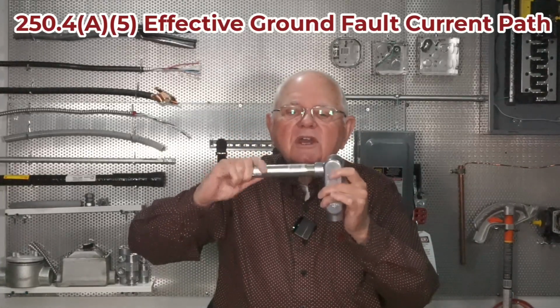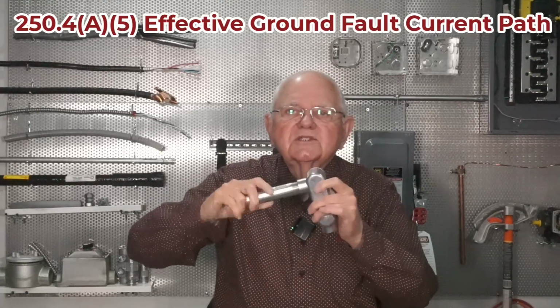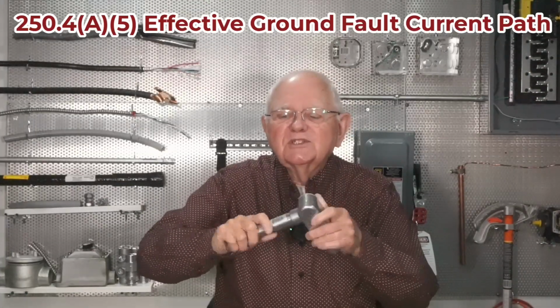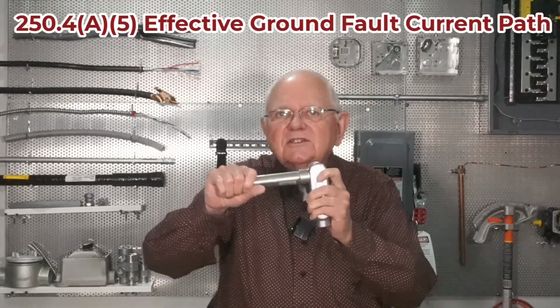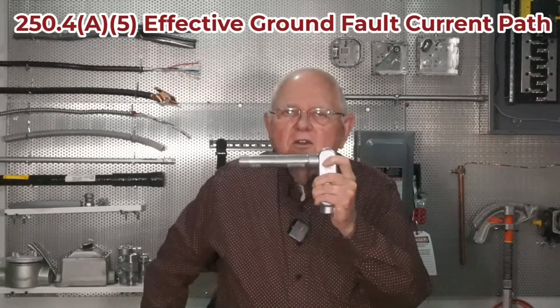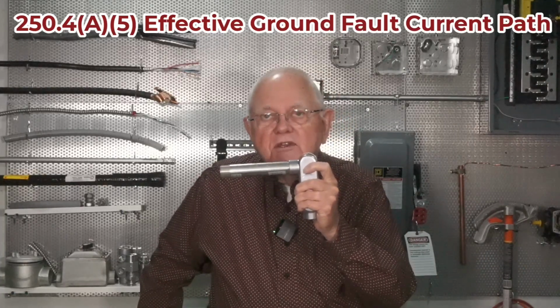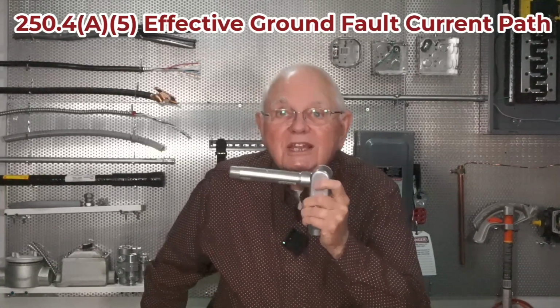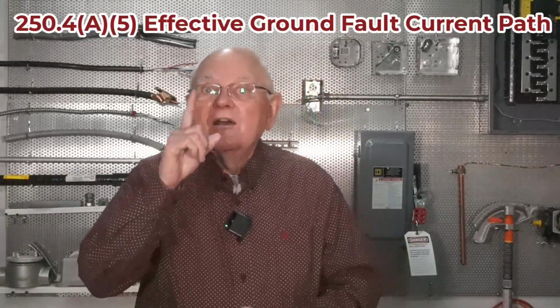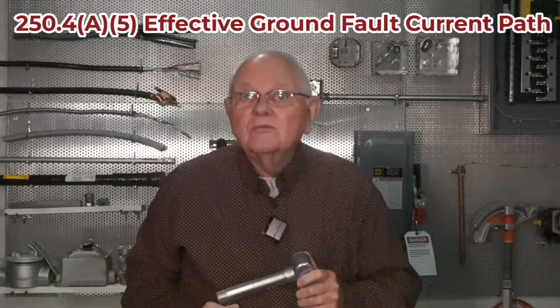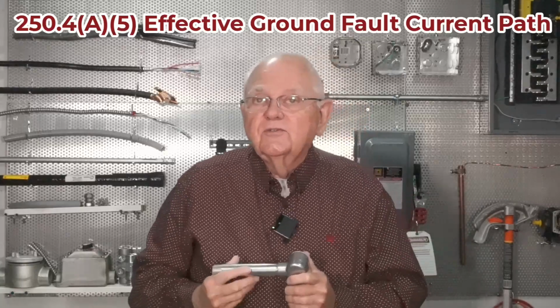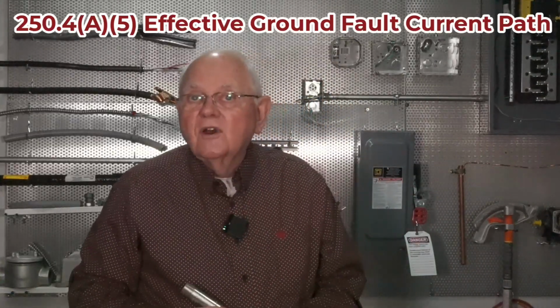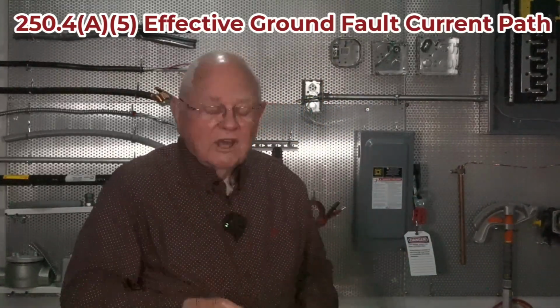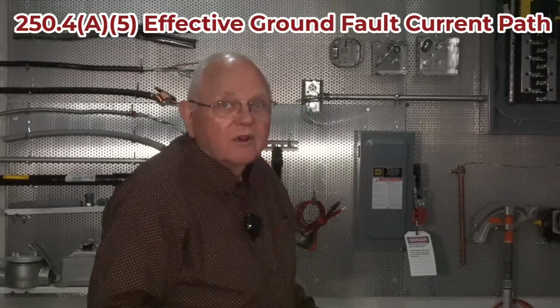So I need to go ahead and make it wrench tight. I get it secure, put a wrench on it, and make sure I've got it good and secure. And now, not only do I have a mechanically sound connection, but I also have one that is electrically sound as well. I now have that effective ground fault current path we talk about in Article 250 that will carry any ground fault current back to the source to allow my overcurrent protective device to operate. So that's important for me.